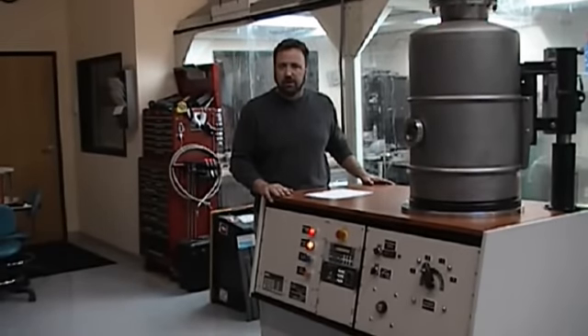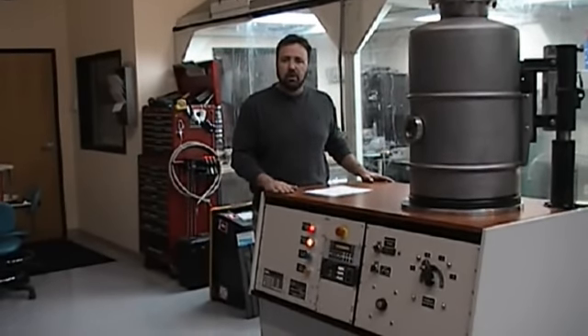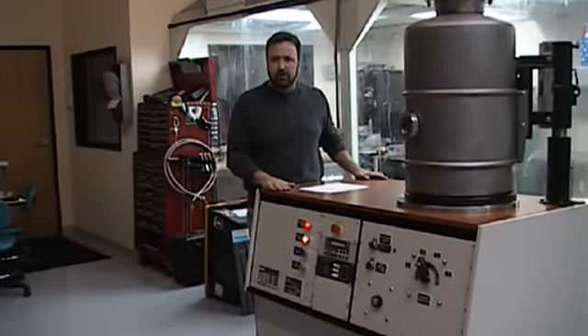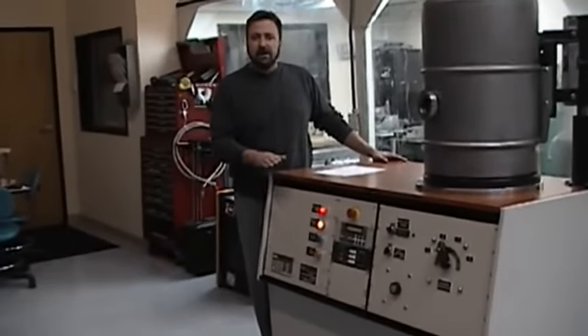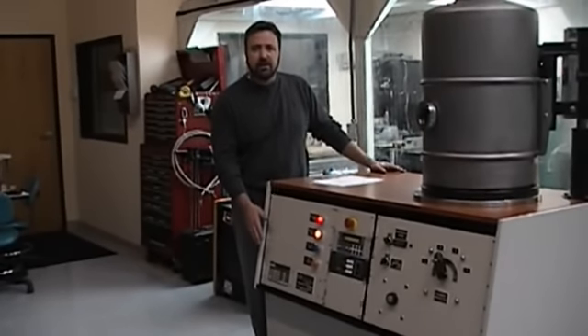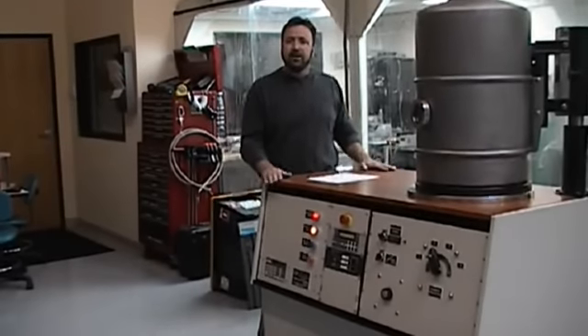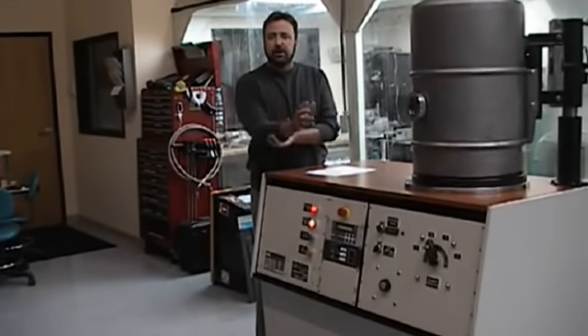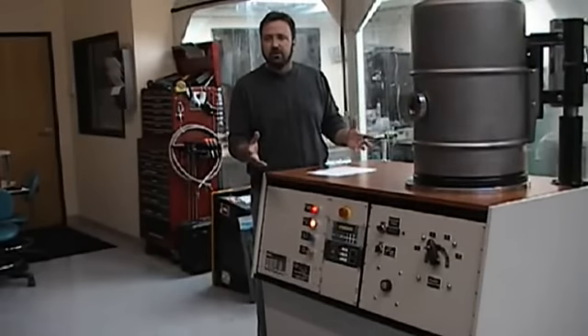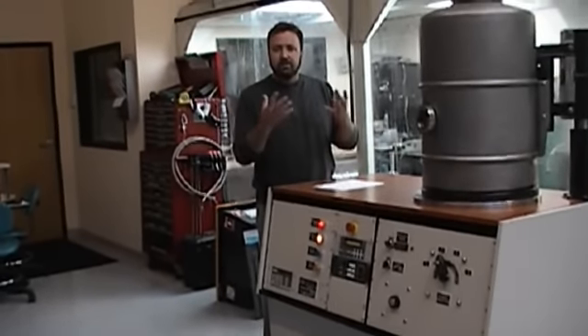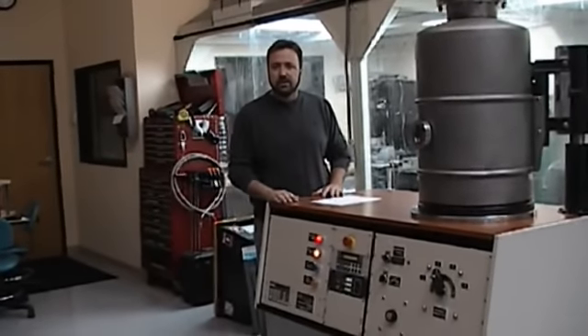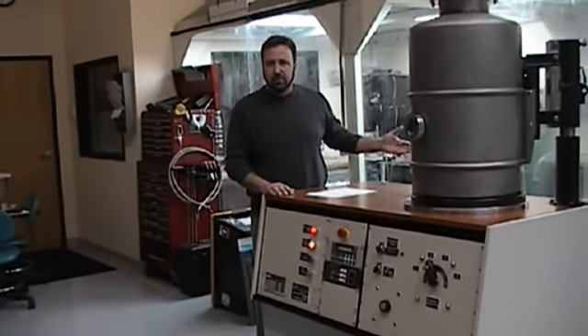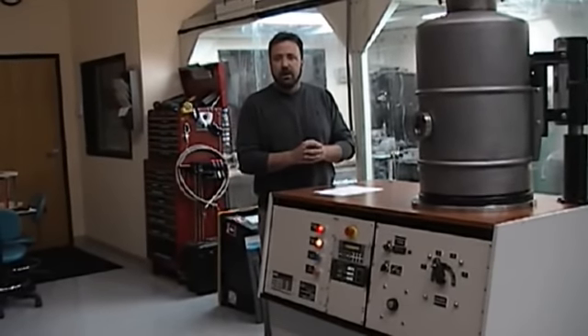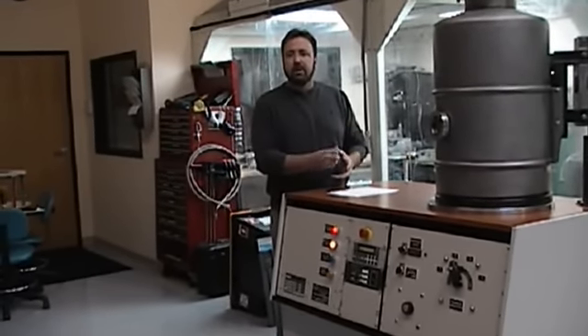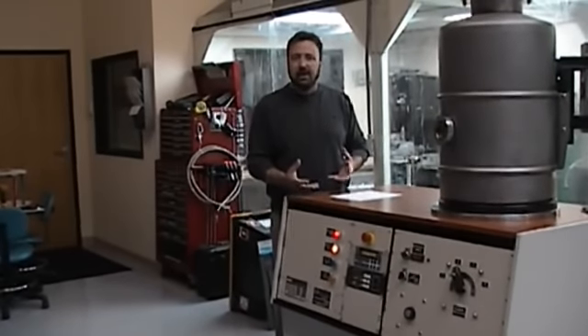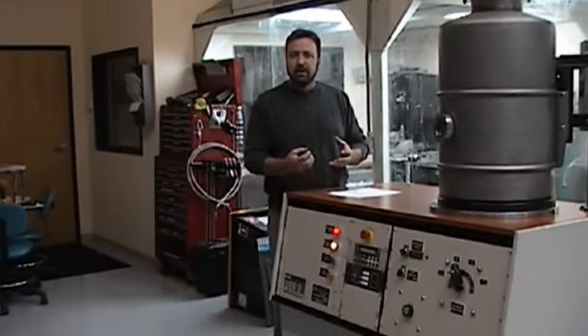If the machine is going to be down for long periods of time, what you want to do is go into a regeneration mode. What that means is, and this is a fully automated system, regeneration will actually bring the cryo pump up to temperature, roughly 300 Kelvin. It brings it up to temperature with heated gas, has internal heaters inside to do this. You'll use dry nitrogen gas to do this. When it brings the temperature up, it will actually be purging nitrogen through the cryo pump.